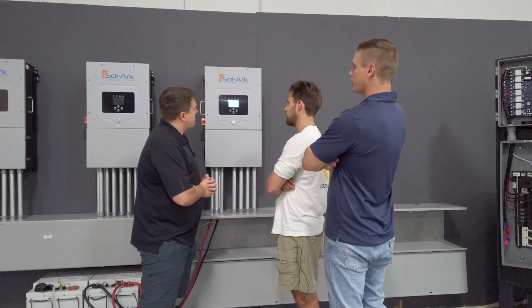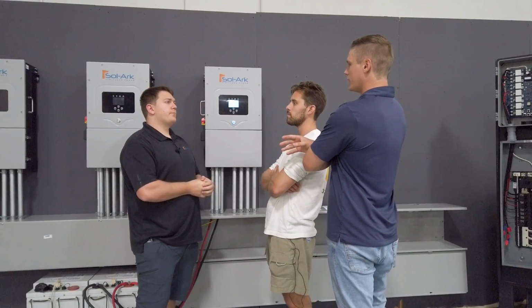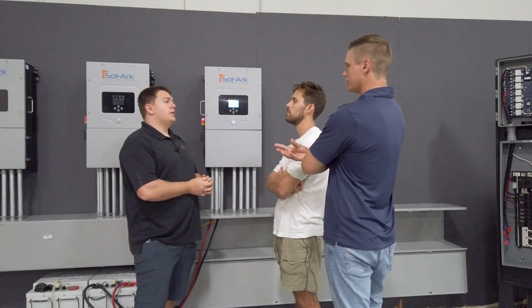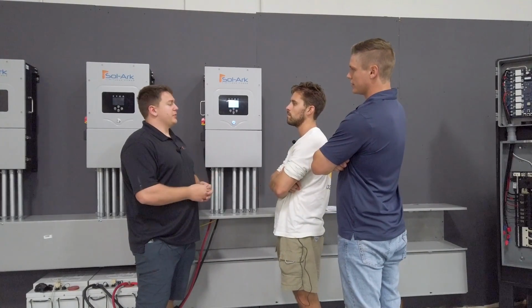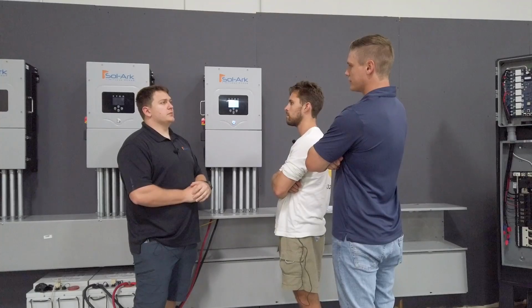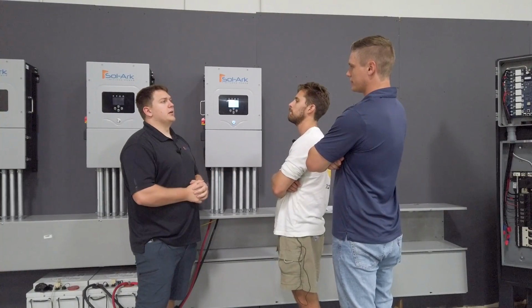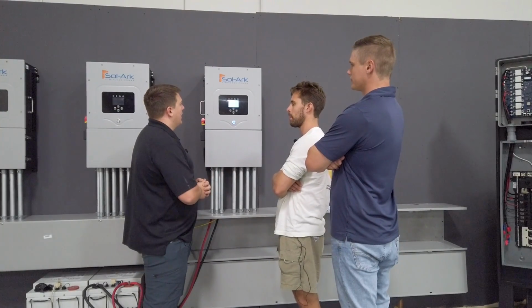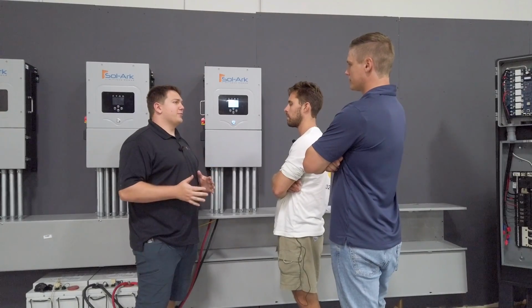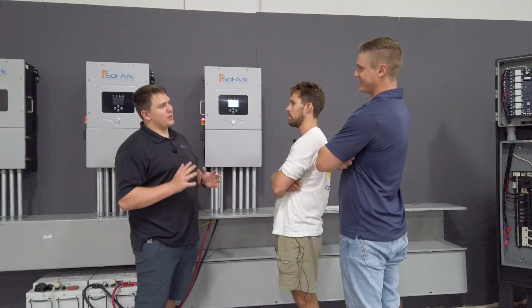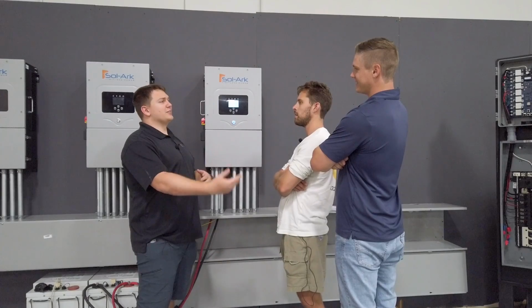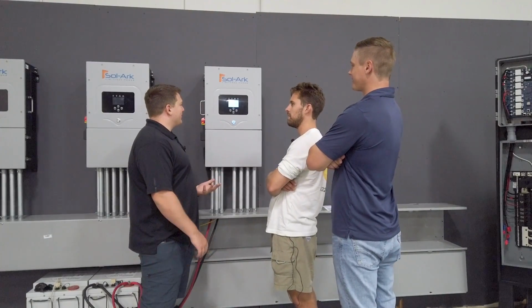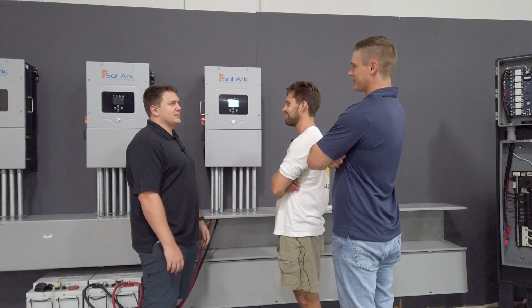And if it does overload more than 5 times, do we have to call Sol-Ark? You don't have to call us, it just requires a manual reboot—you come and hit the power button, wait for it to turn off, then turn it back on. It takes a few minutes. But generally speaking, if you did get 5 overloads in a row, we want you to go figure out why that happened so it doesn't overload again. But if it's less than 5 times in a row, don't worry about it, it'll just take care of it.